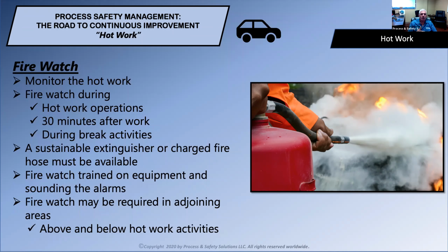Firewatch may be required in adjoining areas. We talked about that a few minutes ago, where you may be doing hot work up on a roof, or you may be doing hot work in an elevated area. Maybe you need the Firewatch to be at the elevated area, but you also may need a Firewatch below to make sure that any sparks or any hot materials that are falling are addressed down there as well.